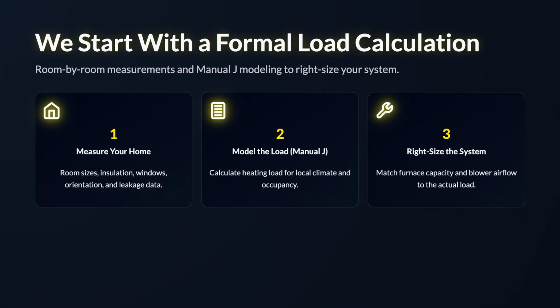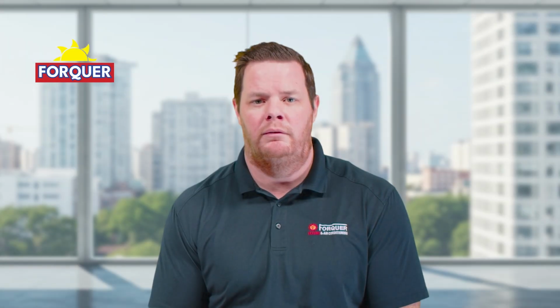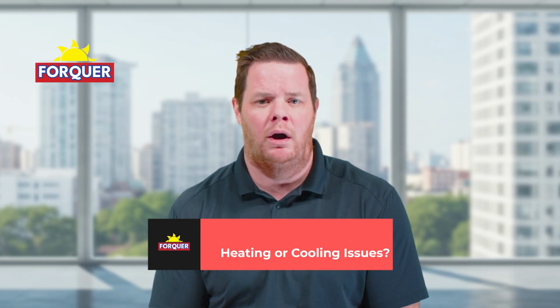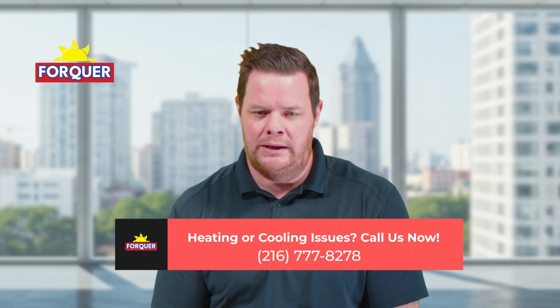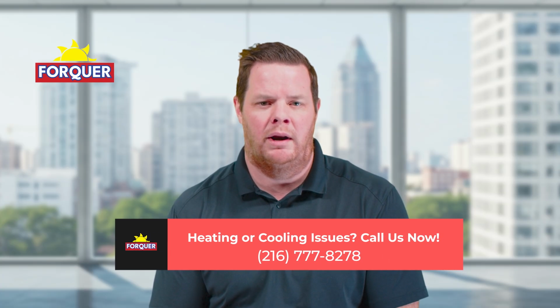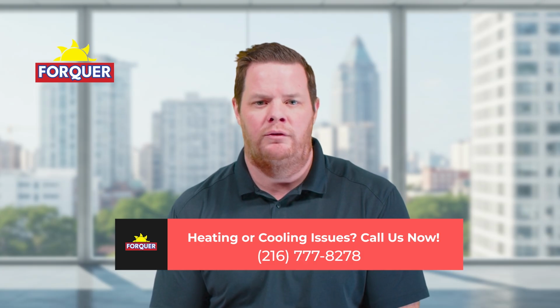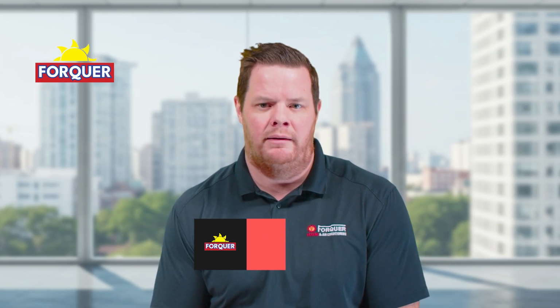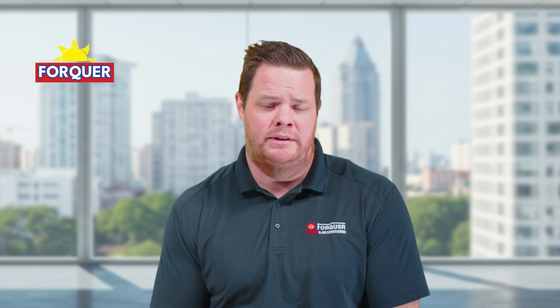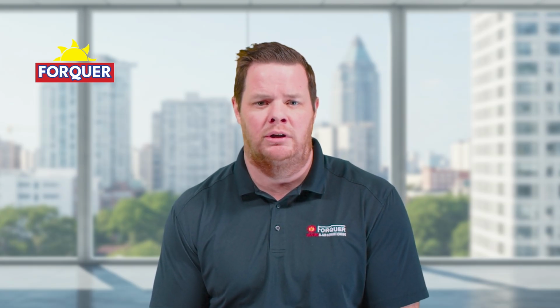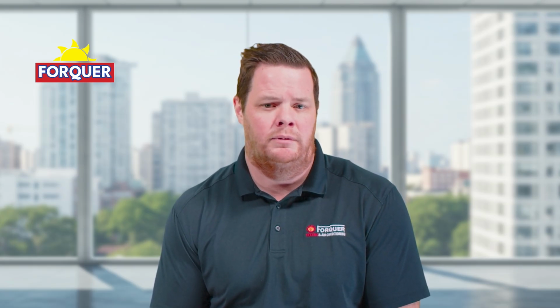What we're going to do when we get in there is a formal load calculation on your home. We'll take into account not only the square footage, but also your ductwork — what can your existing ductwork handle? 99% of the time, we're doing whatever we can to avoid major ductwork modifications, because that gets very expensive and often unrealistic, especially if your ducts run through a finished basement or finished space.